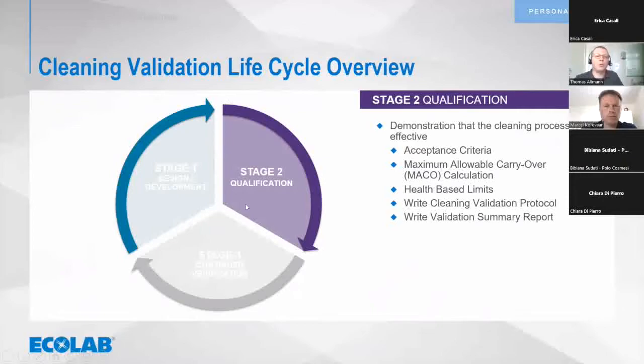If you then go to qualify your equipment, you will demonstrate that the cleaning process is effective. You clean down to your allowable carryover, and it can be 10 ppm, it can be a calculated permitted daily exposure value or health-based exposure limit, or whatever. And you would have to document that in your protocol.